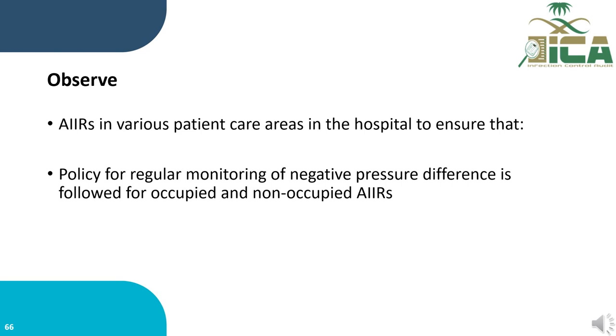You need to observe airborne infection isolation rooms in different patient care areas in the hospital to ensure that the policy of regular monitoring of negative pressure difference is followed for the occupied and non-occupied airborne infection isolation rooms. If it is occupied, you will observe the daily monitoring. If it is unoccupied, you will observe the weekly monitoring.